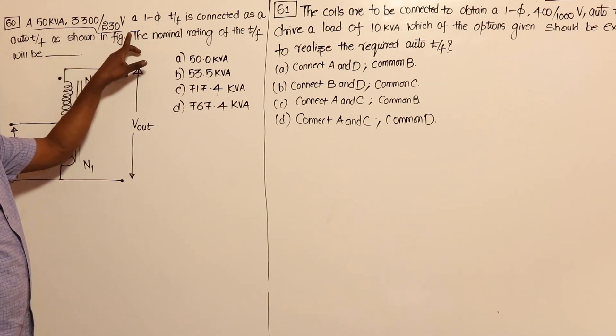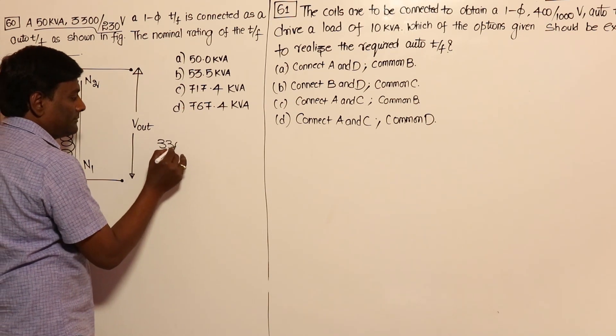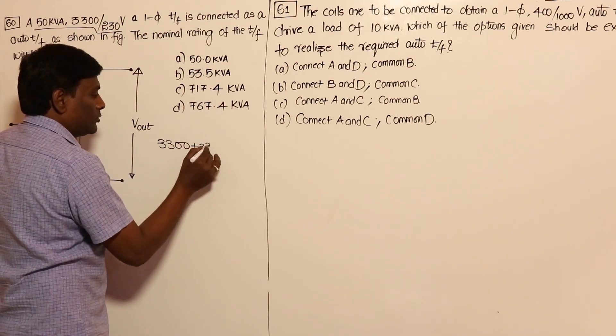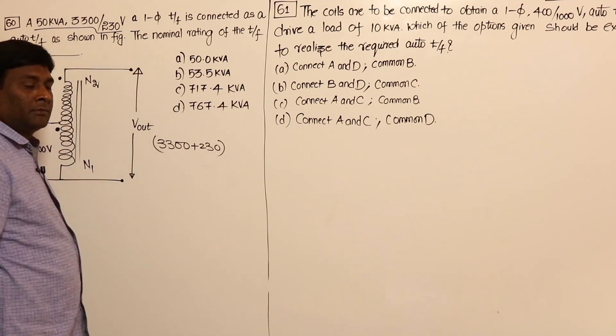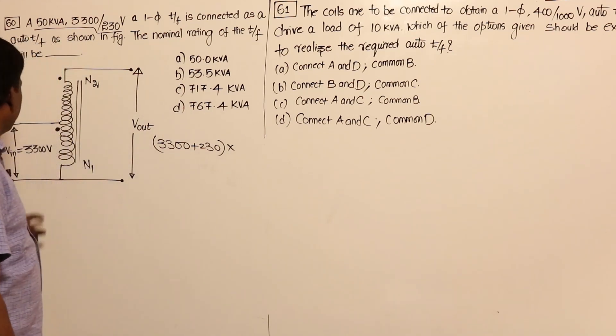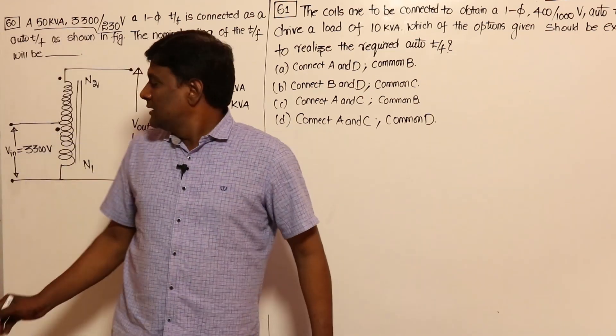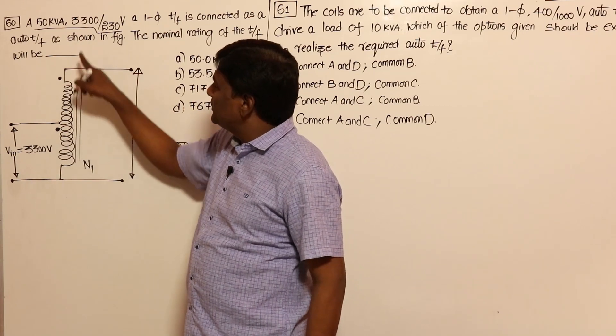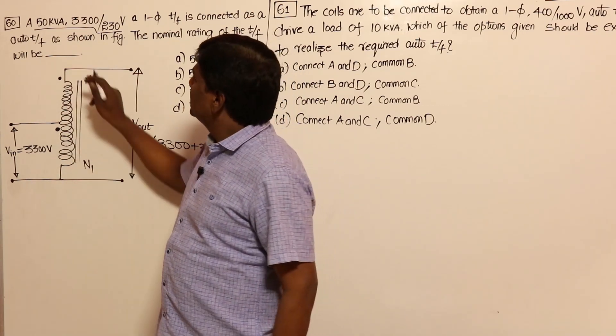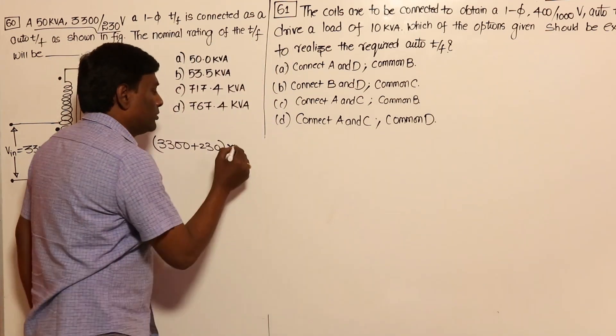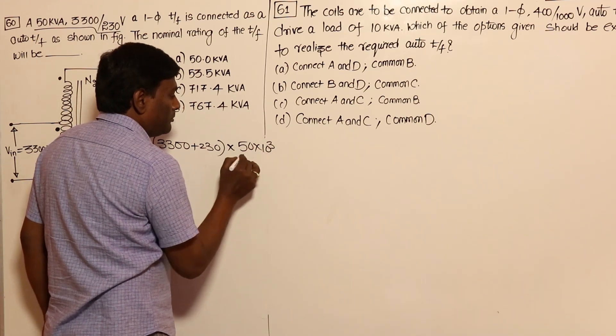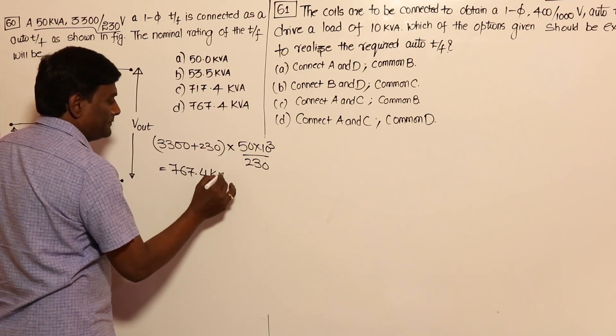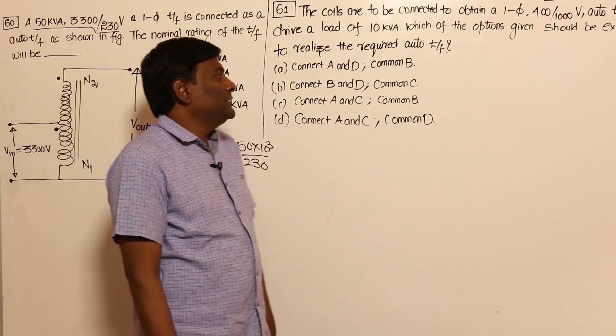For an aiding connection, the output voltage is 3300 plus 230, giving the total additive voltage. The current is 50 kVA divided by 230, which equals 217.4 amperes. Multiplying this out gives the nominal rating of the auto transformer as 767.4 kVA.